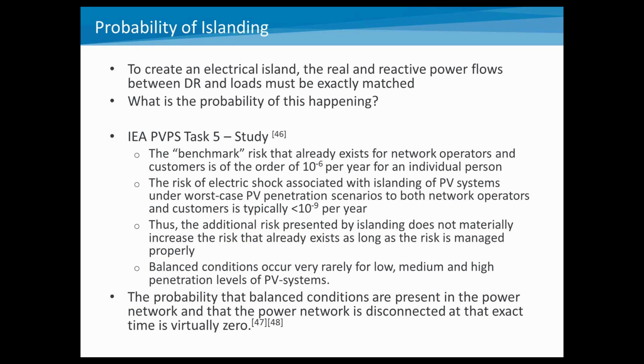Because the fact is, no matter what kind of distributed generation you potentially have, to create an island that sticks around and sustains itself, you have to have a closely matched real and reactive power balance. And over time, that power balance can't change.